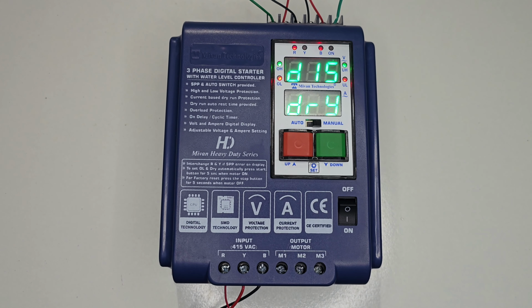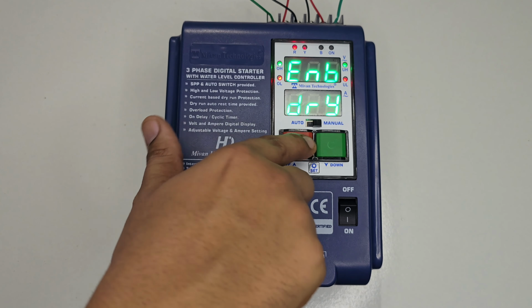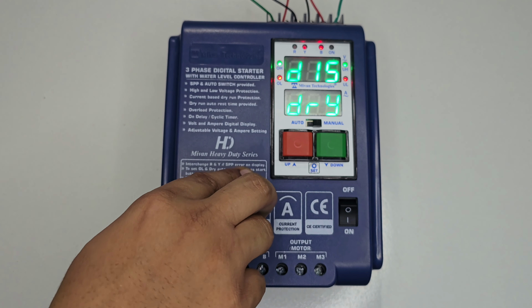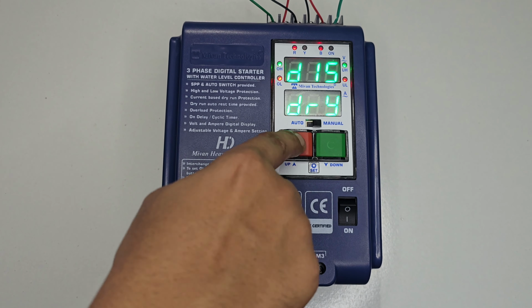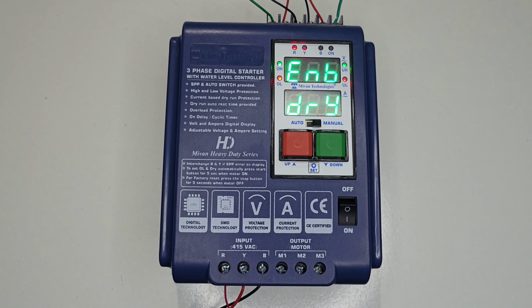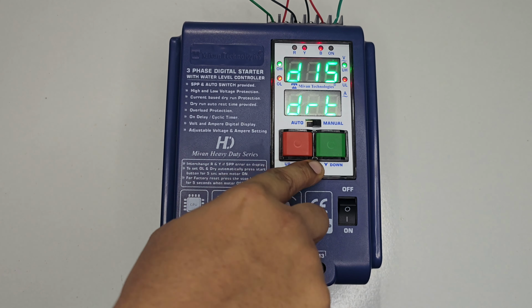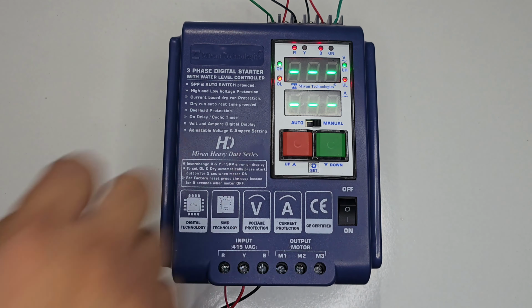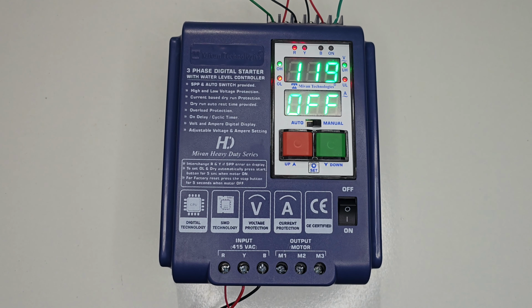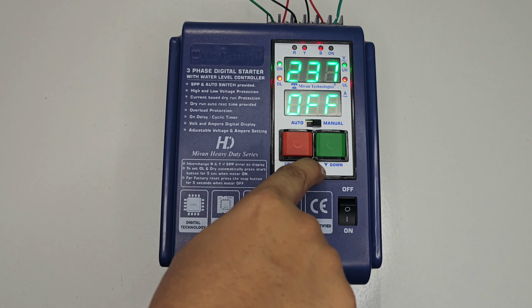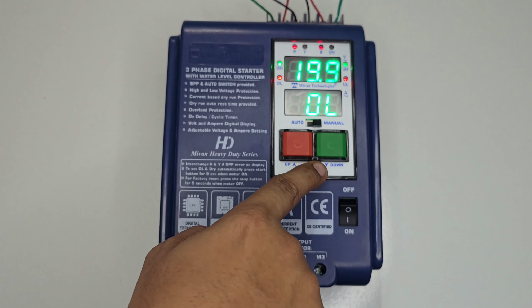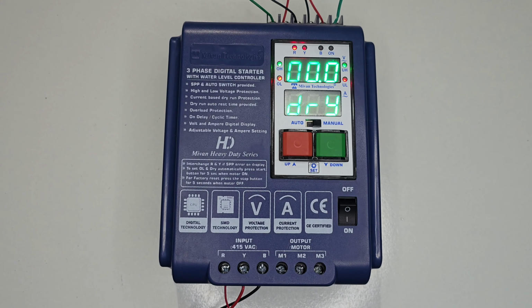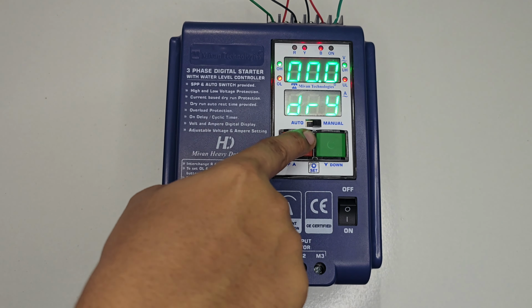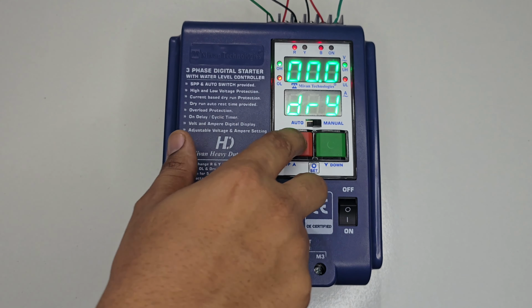Here you can see the dry enable disable option. By pressing the up and down key, you can enable and disable the dry running setting. Make dry enable and press the set button to store the value. When you have enabled the dry running from the password, you can see a dry option in the main menu. Now in the main menu, press the set button. You can see the overload. Press the set button. Here you can see a dry value option. You can set the dry current by pressing the up and down key and press the set button to store the value.